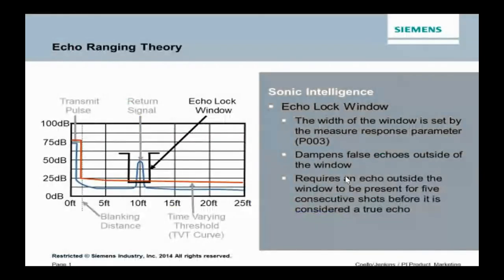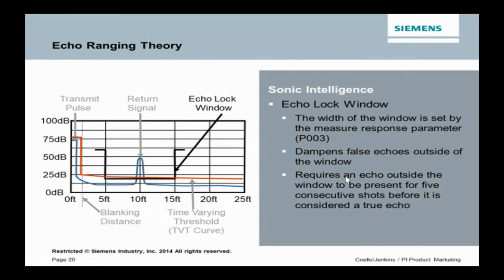Okay. Probably the most misunderstood parameter within the Hydroranger, Multiranger family, and subsequent radar is something which is called response rate, or in old Hydroranger speak, it's parameter P003. And what this does is this is setting the width of something called an echo lock window. Now, the echo lock window doesn't actually show up. I've kind of put one on here just to kind of show what it's doing. Doesn't actually show up in the echo profile, but I'll give you an idea what it does. Okay. In that parameter, you have a choice of slow, medium, fast. If this is an example of a slow response, here's an echo lock window for a medium, and here's an echo lock window for fast.